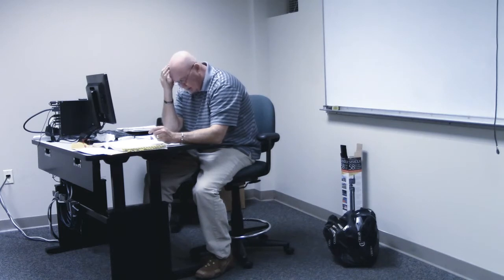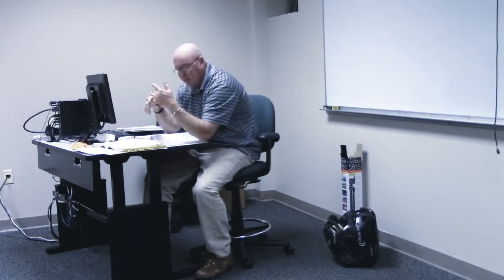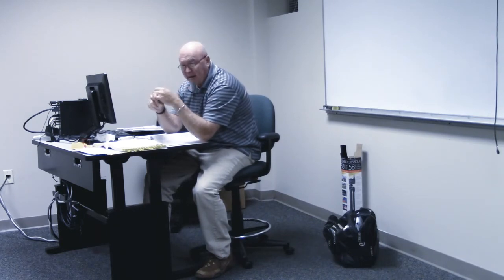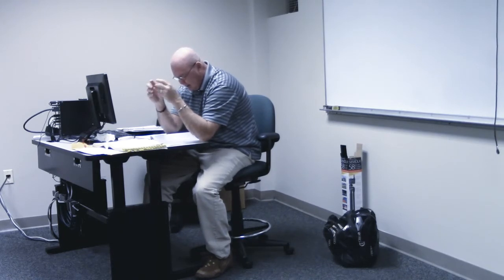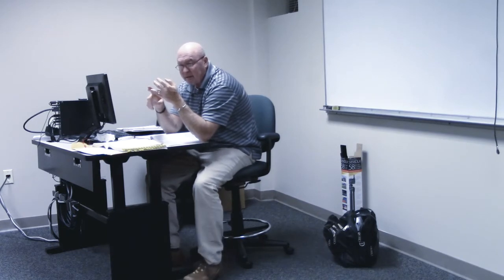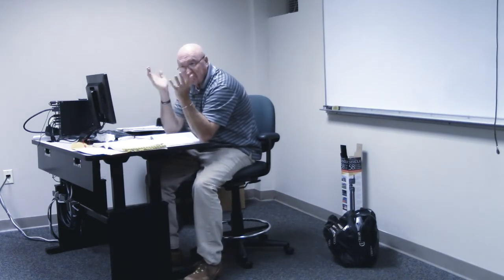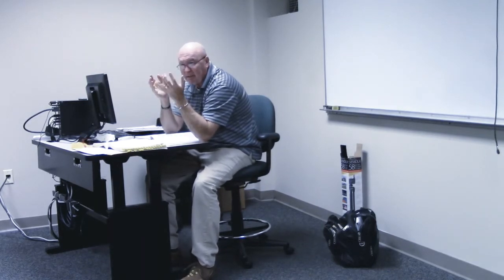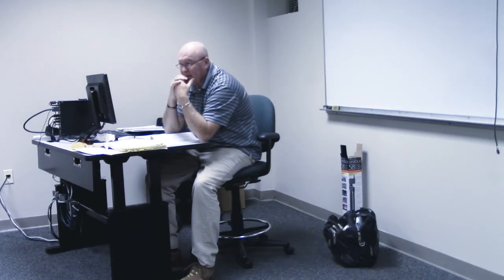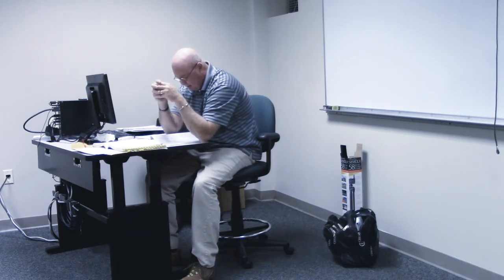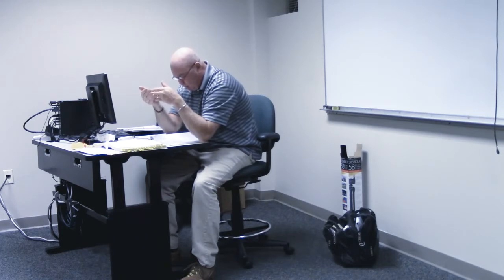The one thing I want you to take note of, under 3.2.0, we're talking about low voltage equipment and instruments. And again, low voltage equipment, like your fire alarm and other things, has to be treated the same, doesn't it? I'd highlight this first paragraph. If you read here, it says low voltage equipment that is typically in contact with patients. What would be something, maybe low voltage, that is connected to a patient? I can't think of anything right now. Equipment that is in contact with a patient or has exposed current carrying elements must be moisture resistant and operate on 10 volts or less, or be approved as intrinsically safe or double insulated equipment. Refer to NEC 517.64.